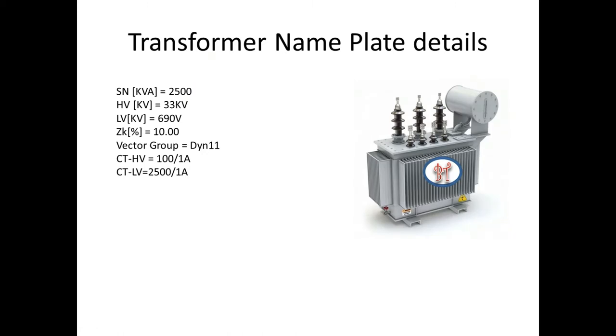Transformer nameplate details: the transformer is 2500 KVA rating. HV side voltage is 33 KV. LV side is 690 V. Impedance percentage is 10%. Vector group is Dyn11. HV side CT ratio is 100/1. LV side CT ratio is 2500/1.